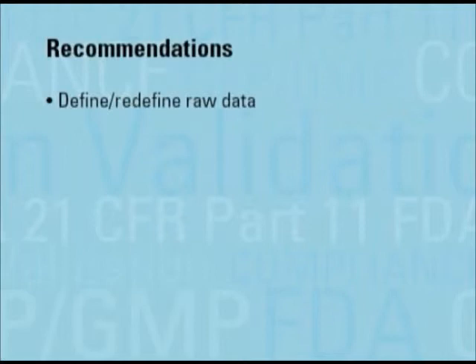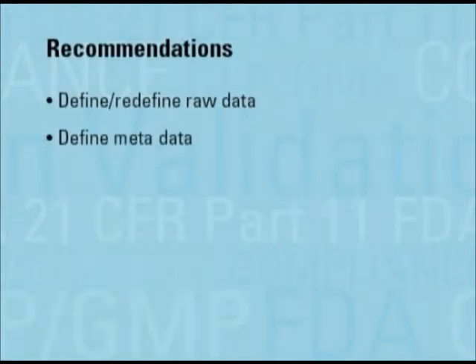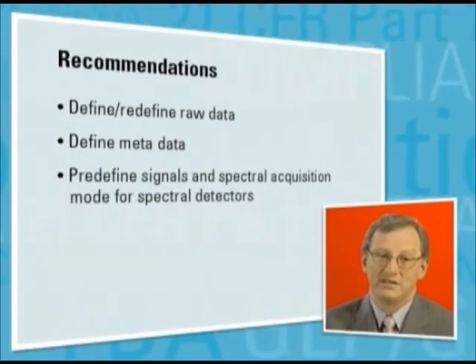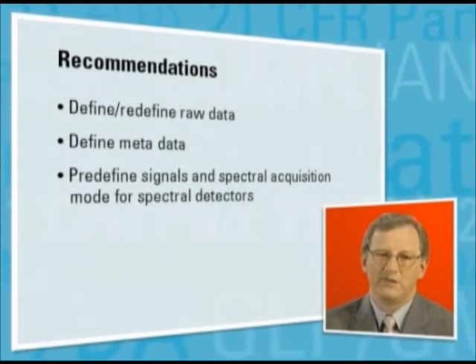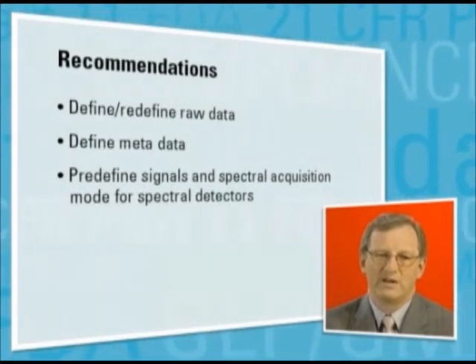I would recommend that you look at the definition of your raw data. Computer printouts are not accepted as an accurate and complete copy, so this is not an option. You should also define metadata in your system — metadata must be archived together with the raw data. In chromatography, these are mainly integration parameters and calibration factors. For spectral detectors, you can save a lot of disk space and database capacity by pre-defining signals and spectral acquisition parameters.